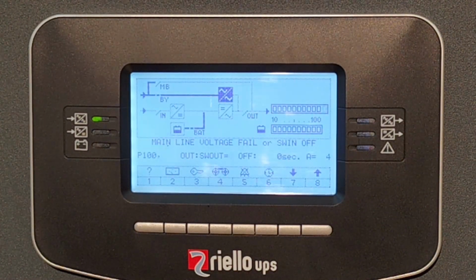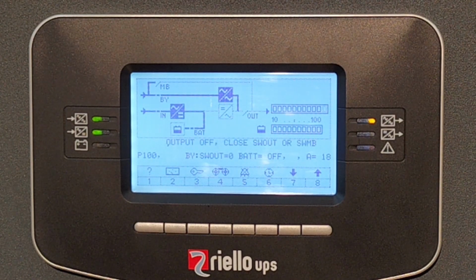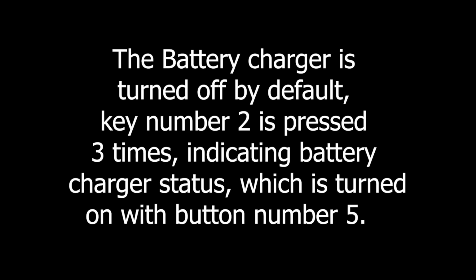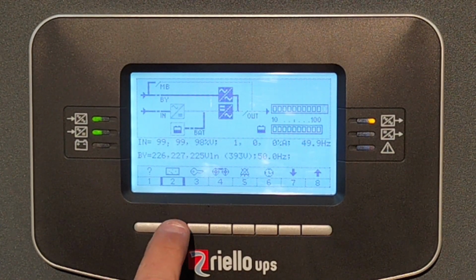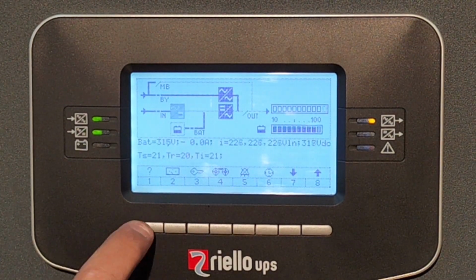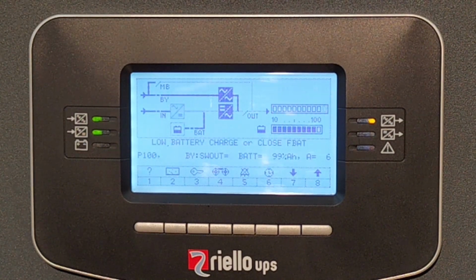Okay, what we're looking at is the display powering up as the SW bypass switch is turned on. So the UPS control is now active. The rectifier and the inverter are off. Only the static bypass is available. Everything else is off. The rectifier symbol flashing indicates that the SW-in, or the main input, is now turned on. Right, SW out is now on, so of course the load now has power.